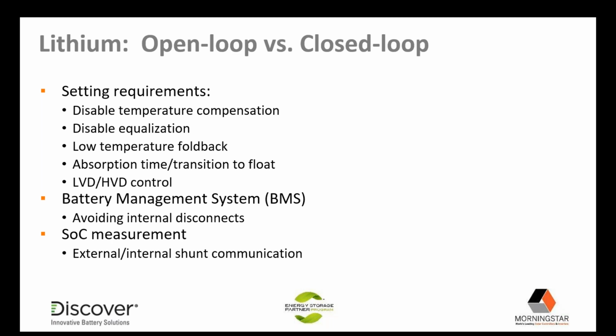And that's why it's very helpful, if possible, to always have the battery management system, either through direct communication or external signaling with a relay or some type of mechanical means, give us a heads up, basically to say, okay, charge controller, you can turn off the PV now. We're going to disconnect from your controller. Again, that avoids any unnecessary complications or potential damage that may occur when you just suddenly pull the plug on the charging source, where our charge controller is very much dependent on the battery for its power operation.